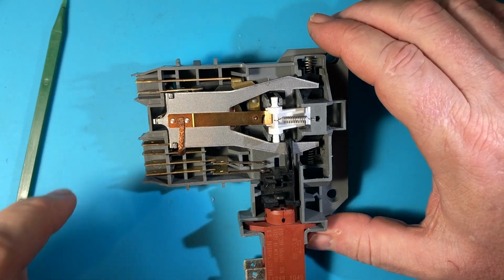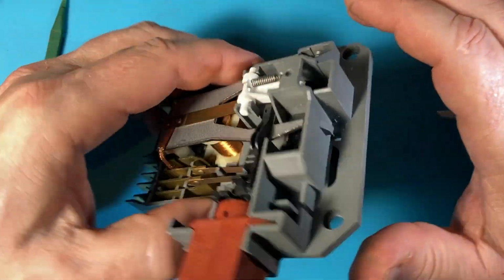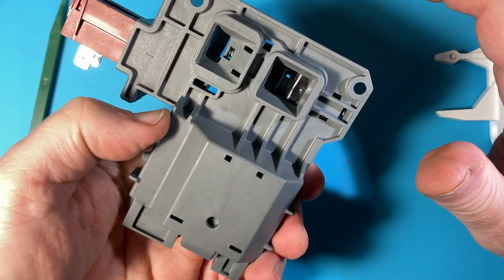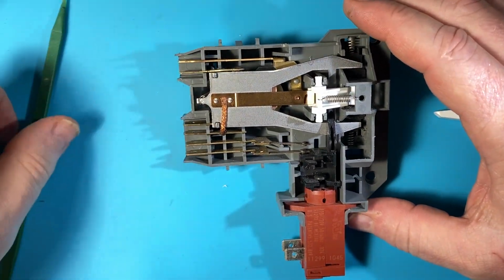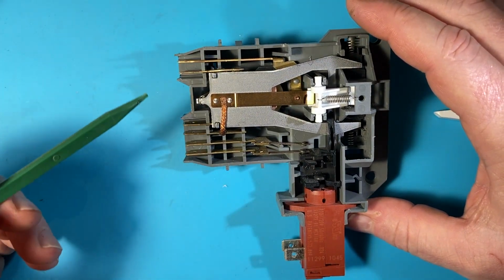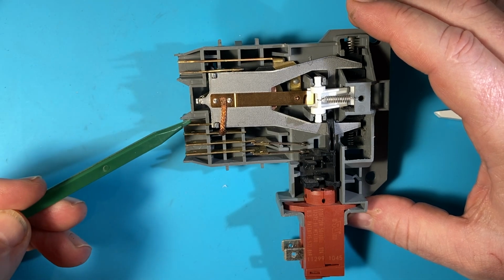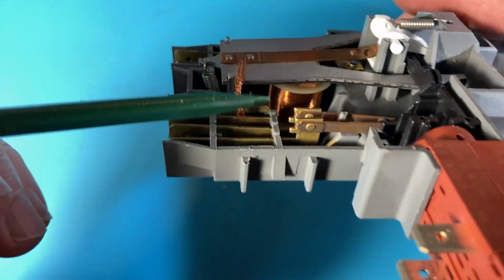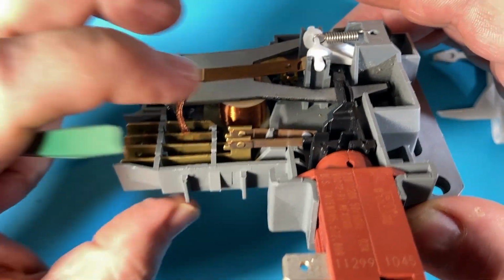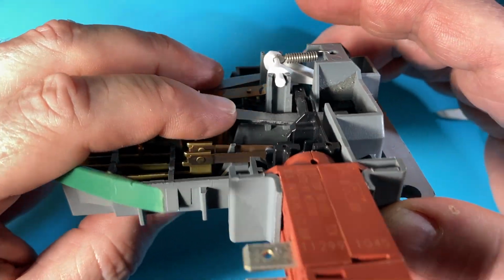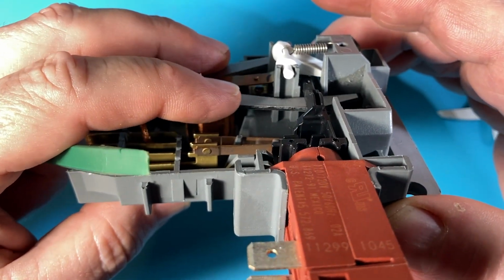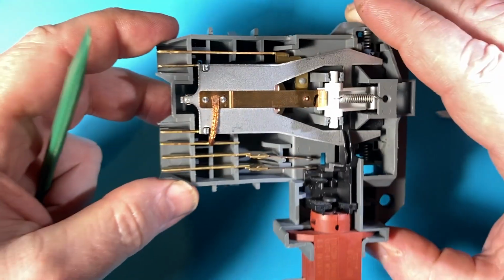The back came off pretty easy, and now that it's open, we can really see how it works. This is the front side that you're all used to, and now the back. If you'll remember, these two are the relay coil, and you can see the relay coil under there. So when the relay energizes, it pulls this bar down. I'm going to call this the locking fork, and you'll see why in a minute.